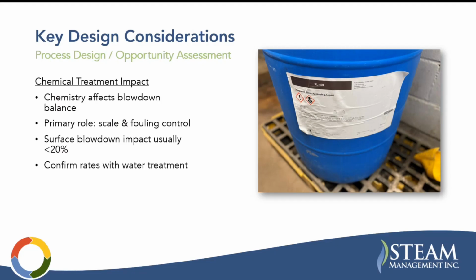One thing to be aware of is that there is an impact on surface blowdown with chemical treatment. There are certain chemicals that are designed to bind or react with dissolved solids, and they say they sink them to the bottom, and then they're being handled by bottom blowdown. But in reality, though, most of the chemicals, their goal is to make the dissolved solids less adherent. So they're more focused on reducing scale than sinking dissolved solids.